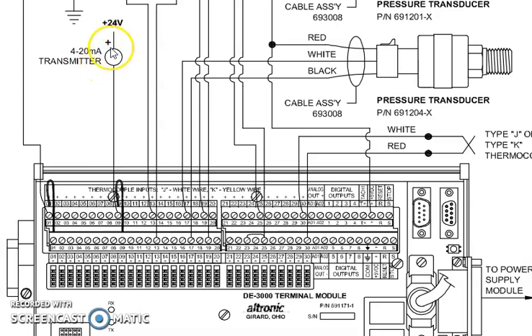But this is an example of a standard 2-wire 4 to 20 milliamp pressure transducer. So we'll have the pressure transducer out on the skid or up under the panel, and we'll have positive 24 volts supplying the pressure transducer. And then the negative wire for the pressure transducer is actually what's carrying the 4 to 20 milliamp current flow signal. And so that's going to connect down to one of the terminals for the associated channel, and your dip switches will be set to 4 to 20 milliamp. Now what that does is that takes this second terminal for that same channel and it connects it internally to ground with a 200 ohm resistor.